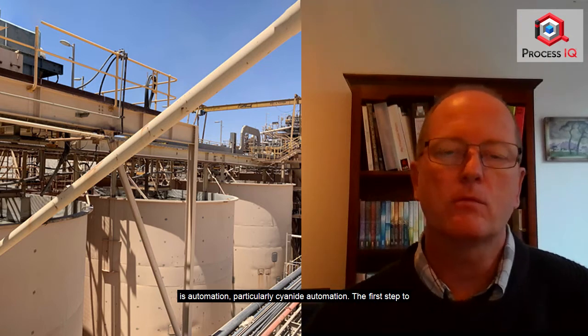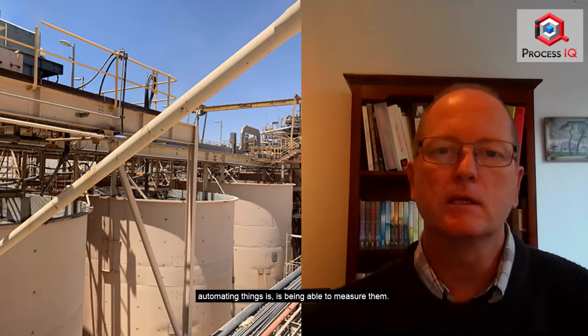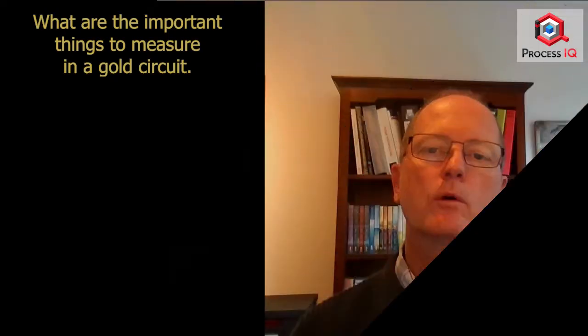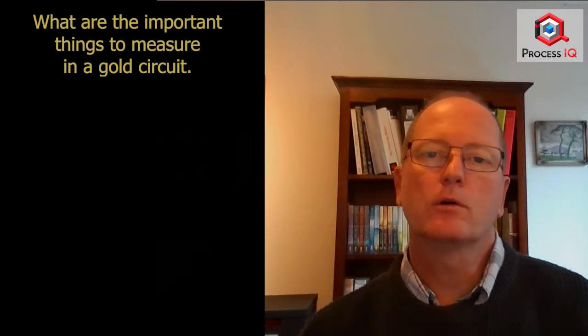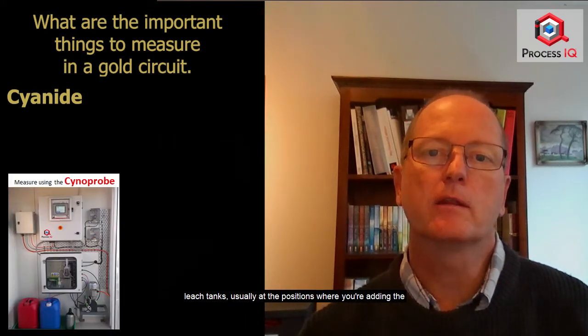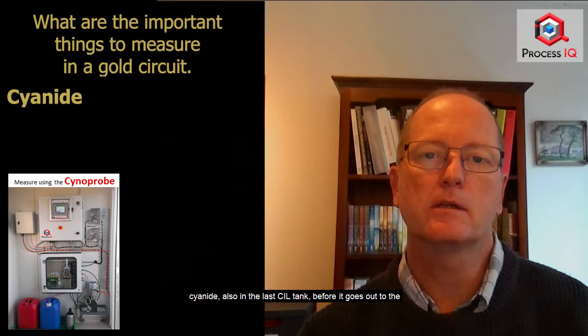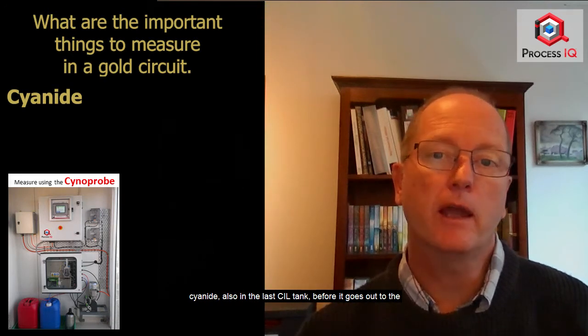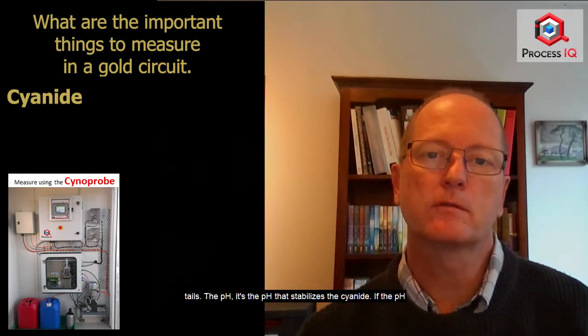The first step to automating things is being able to measure them. So what are the important things to measure in the gold circuit? We mentioned the cyanide. It's really important to measure the cyanide in the leach tanks, usually at the positions where you're adding the cyanide, and also in the last CIL tank before it goes out to tails.